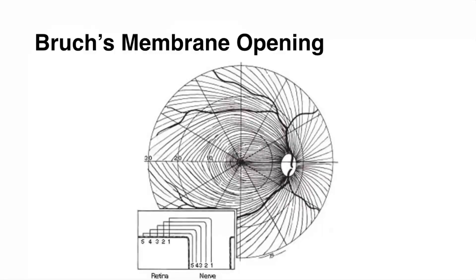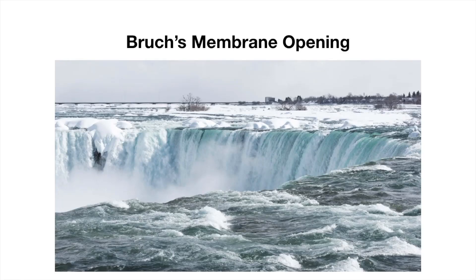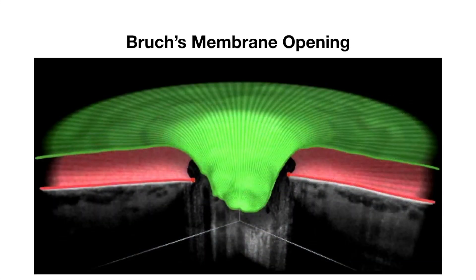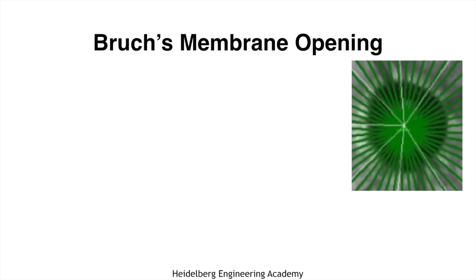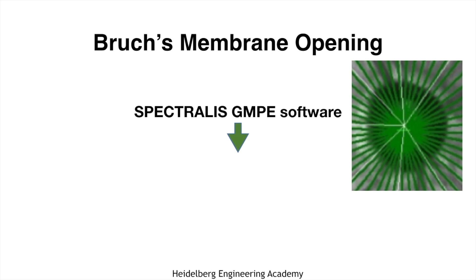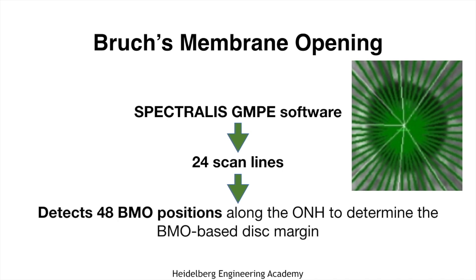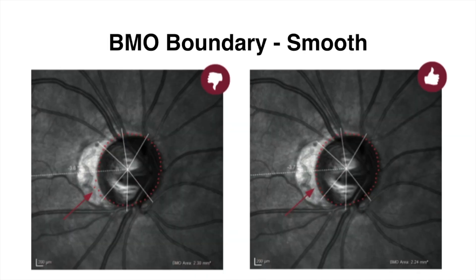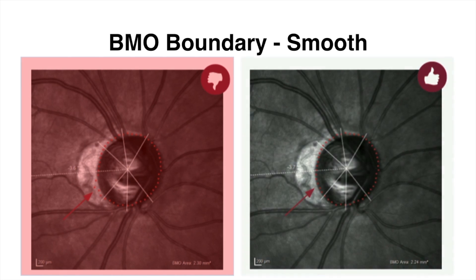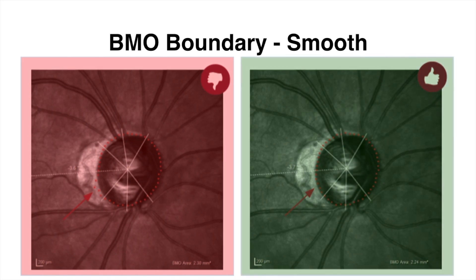Bruch's membrane opening: imagine the retinal nerve fiber layer projecting into the optic disc like water falling into a waterfall — this helps in understanding the concept. With the Spectralis Glaucoma Module Premium Edition software, there are 24 scanned lines, so totally 48 BMO positions are detected along the optic nerve head to determine the BMO-based disc margin. The BMO-based disc margin should be smooth; an irregular margin indicates an erroneously performed test.